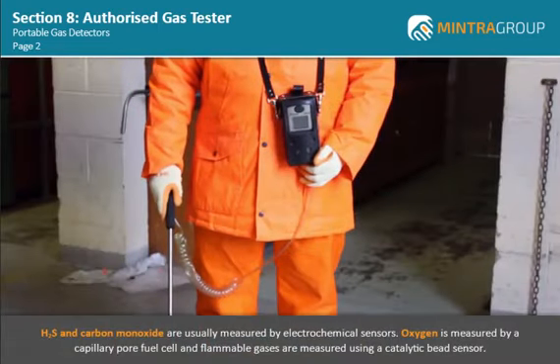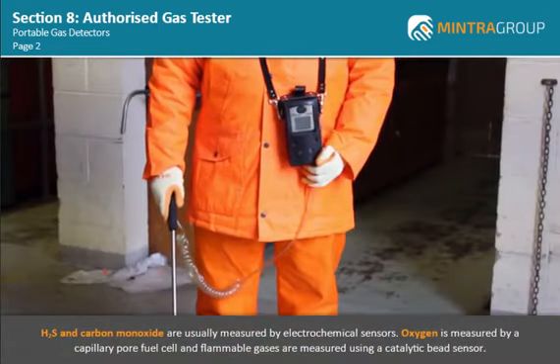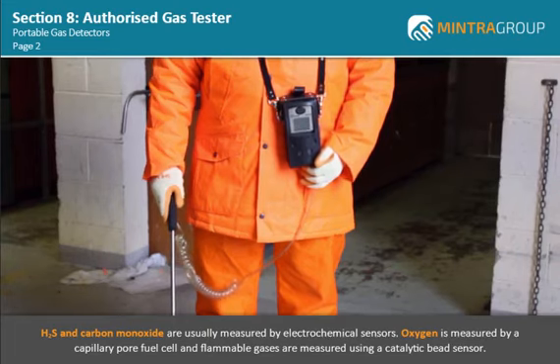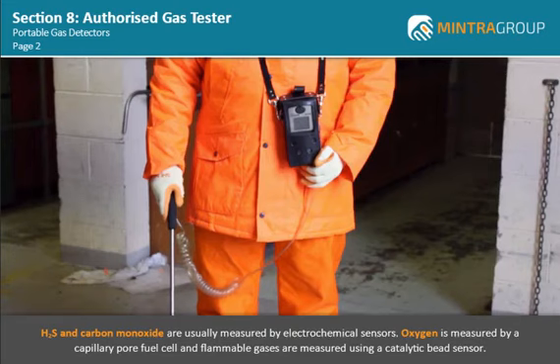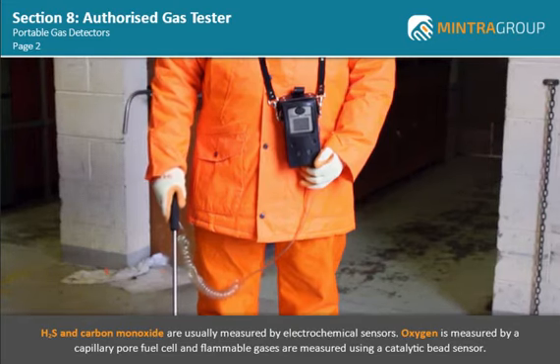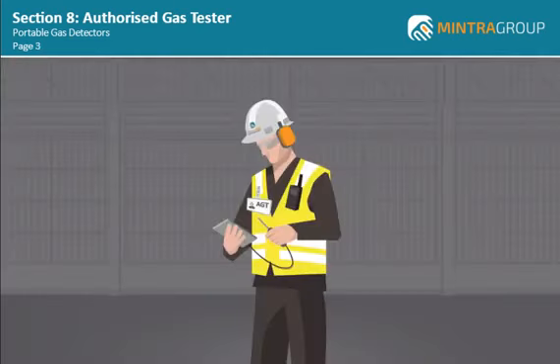H2S and carbon monoxide are usually measured by electrochemical sensors. Oxygen is measured by a capillary pore fuel cell, and flammable gases are measured using a catalytic bead sensor. Although as the AGT you will normally be involved in the use of portable gas detection systems, you should be aware of some of the other types of gas detection systems that are in use.